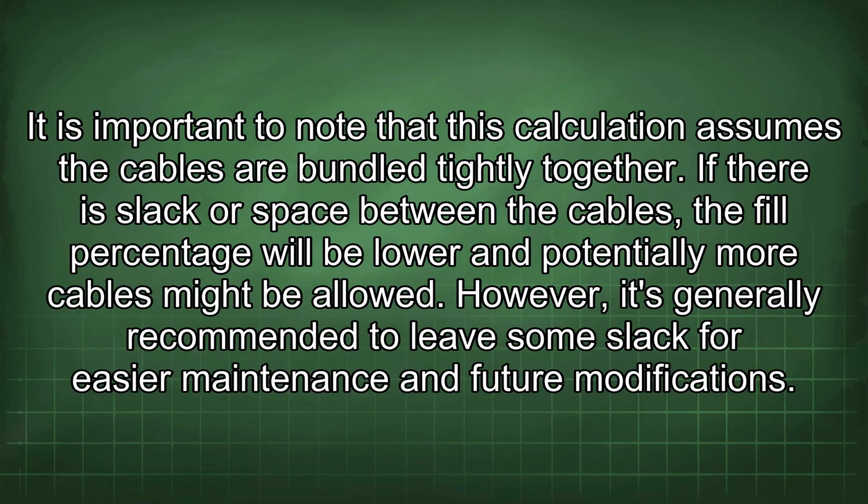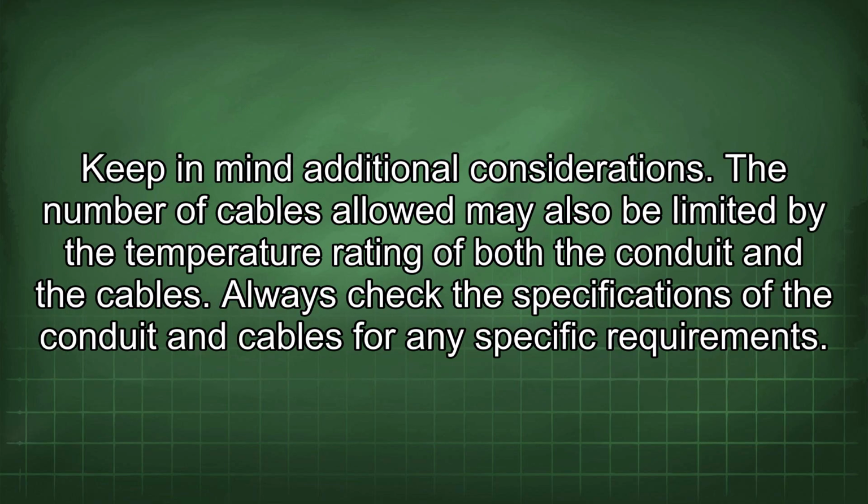If there is slack or space between the cables, the fill percentage will be lower and potentially more cables might be allowed. However, it's generally recommended to leave some slack for easier maintenance and future modifications. Keep in mind additional considerations. The number of cables allowed may also be limited by the temperature rating of both the conduit and the cables. Always check the specifications of the conduit and cables for any specific requirements.